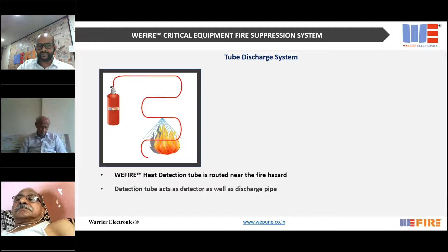Let's look at the solution that we have for now. So we have two types of systems. One is the tube discharge system, which we'll discuss now. So we have a cylinder and we have a detection tube. We do not use conventional smoke detectors or flame detectors, although we can use those as well, the industrial grade. However, this system consists of a linear heat detection tube which is routed across the fire zone. This tube acts as a sensor as well as the discharge agent. The discharge gas will be discharged through the very opening of the tube. Let's look at the live video.